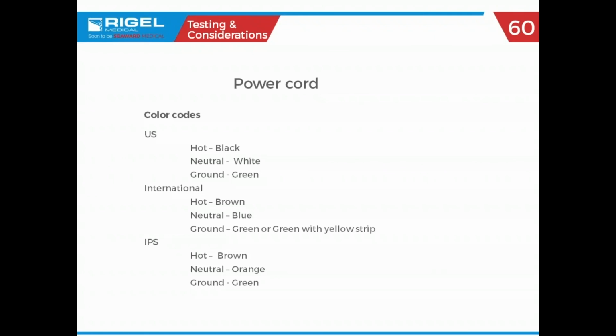So you have to test with a normal grounded conductor. Sometimes that means running an extension cord. Sometimes it says in the isolation transformer box, you put a temporary shunt in to take the low end of that transformer connected to ground. Be sure to remove it. But you have to have a ground to test leakage current to ground, and isolated power sources don't have ground. Now you have on the back of a lot of equipment the equal potential point that a lot of people will tie all together and go to a ground point. So all the equipment are sitting at a relative same potential, but there's no real ground.